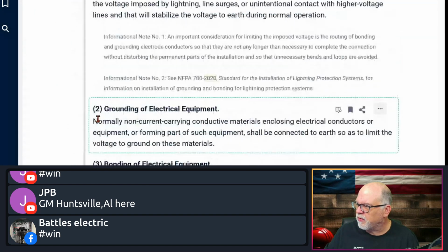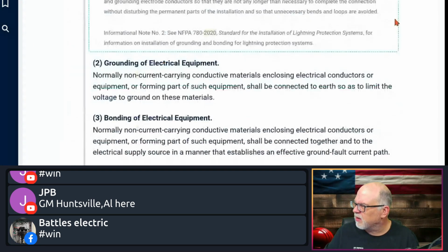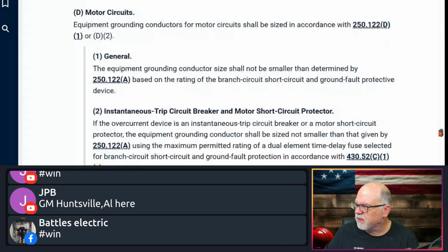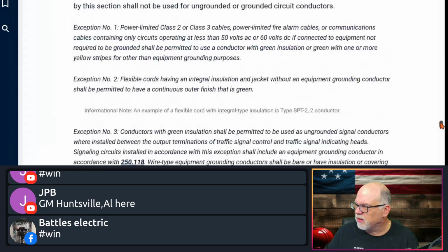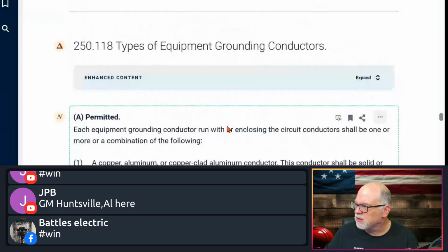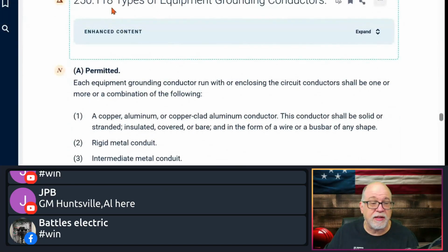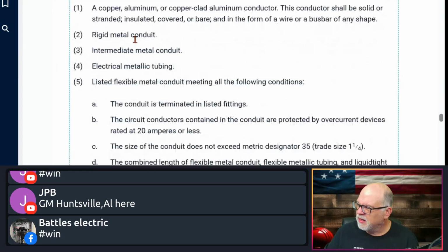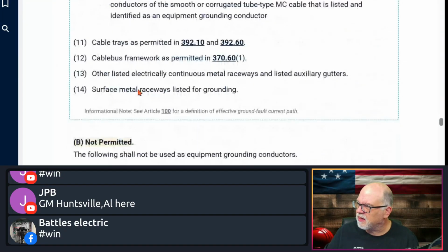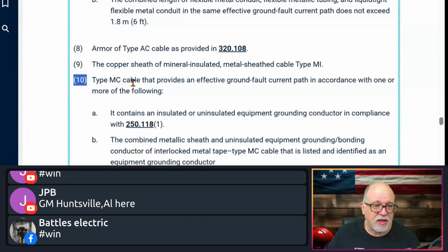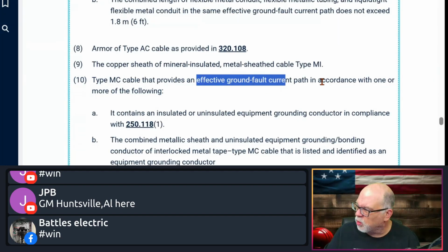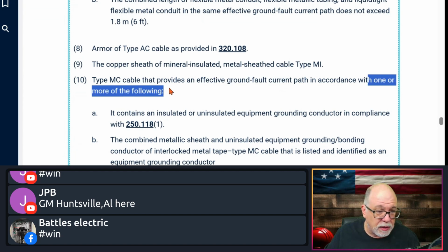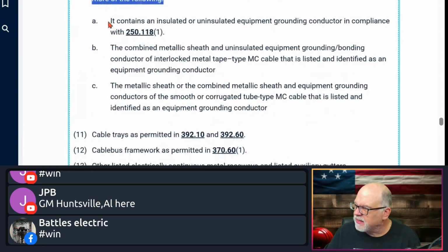Let's get down here to 250. Let's see here, 118. Let me get you down. I always like showing you just so we can end on positive notes. There's 250.118. These are the different types of equipment grounds. And you get down to 10 right here, MC. And this is a good little lesson for folks. It says MC cable that provides an effective ground fault current path in accordance with one or more of the following. One or more. Number one, it contains an insulated or uninsulated equipment grounding conductor in compliance with 250.118(1).